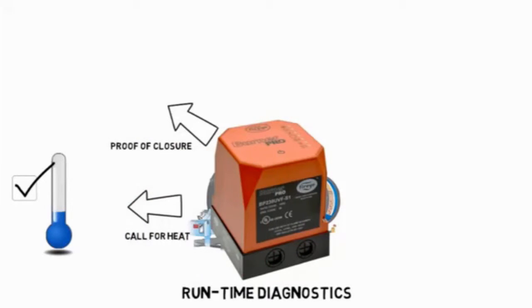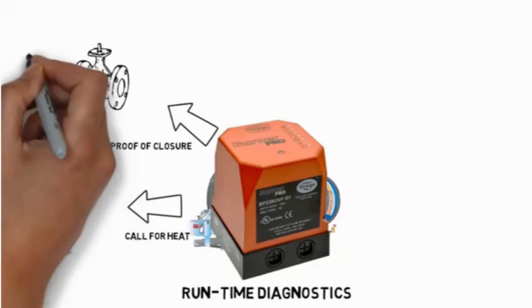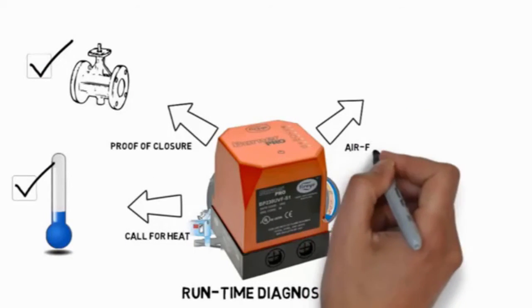Proof of valve closure checks for wiring problems or faulty fuel valves. Air flow proving cycle ensures a proper combustion environment.